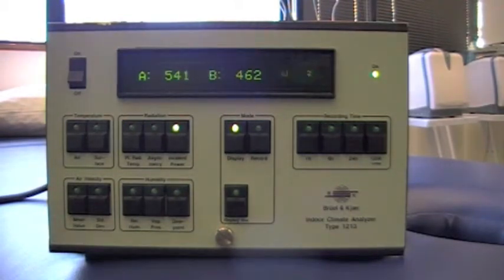This difference in radiant heat now that we've got direct sunlight coming through the windows is also reflected in the radiant heat energy on the two surfaces. You can see that the radiant heat on the A surface has gone up considerably over the value that we had before. Whereas the B value is fairly close to what we had previously with blinds shut.